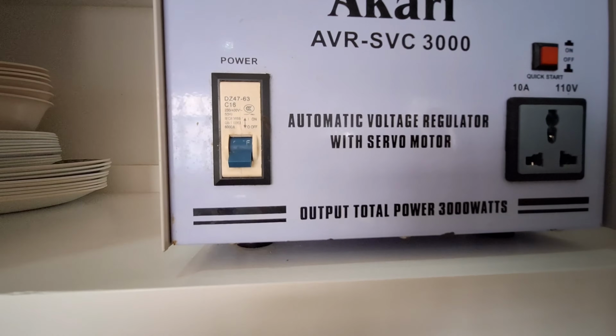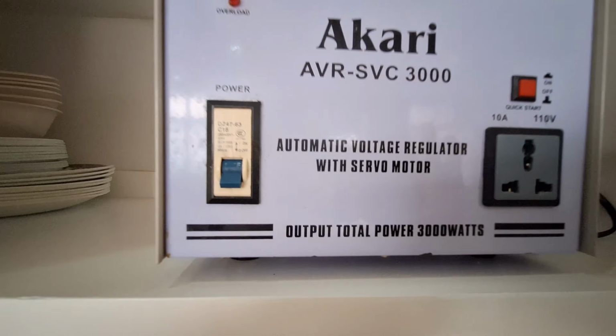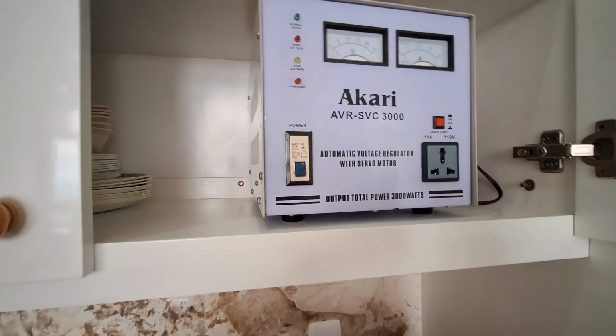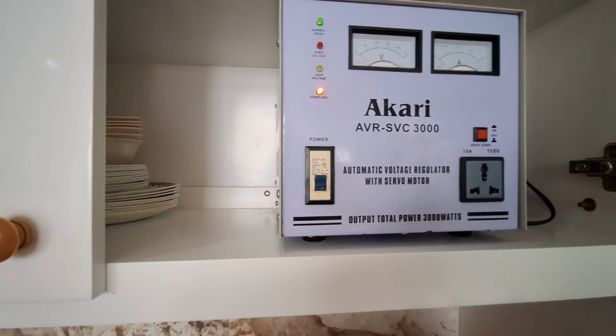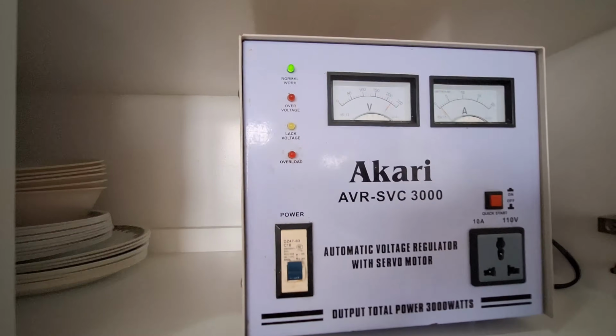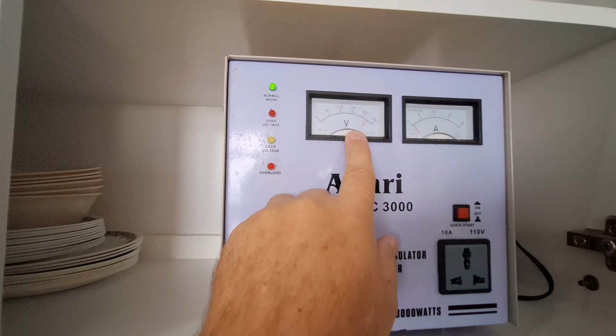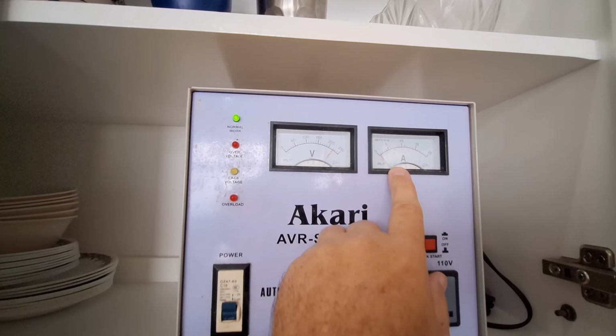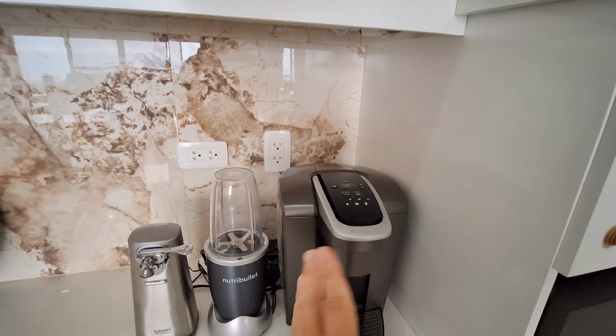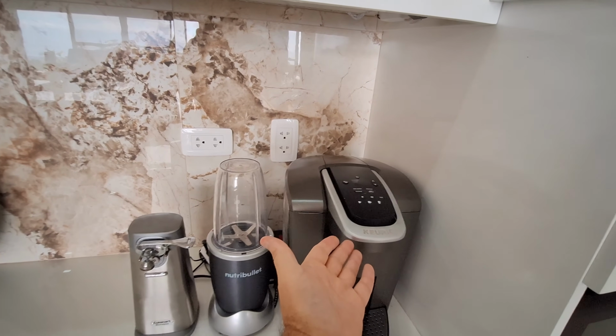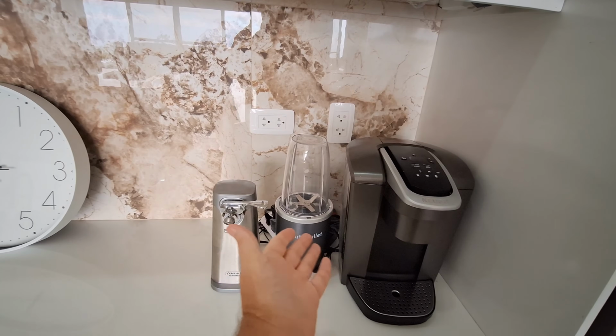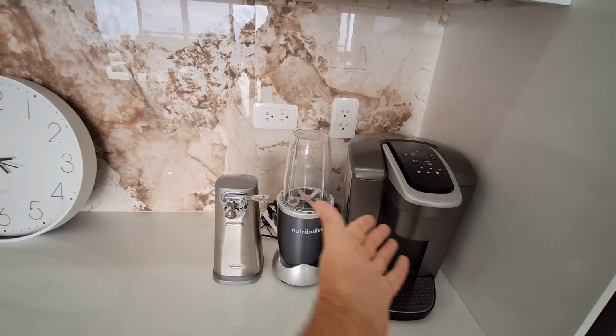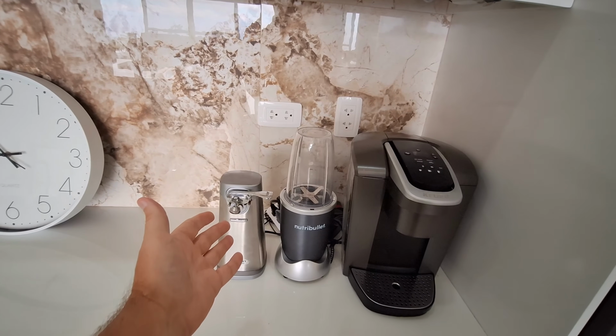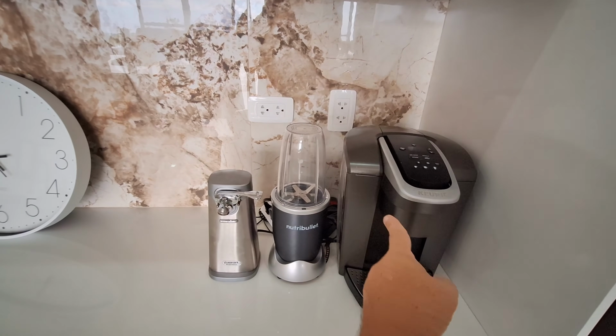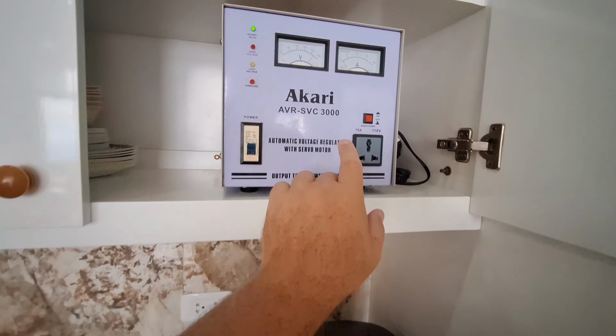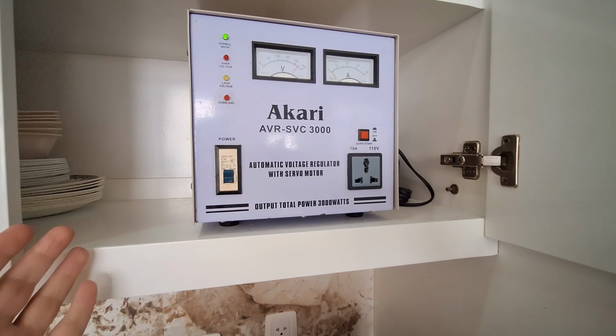So it's an automatic voltage regulator and also a step-down transformer - pretty simple. You put it on the circuit breaker, and you can see the 220 volts coming in with nothing going out yet. If I turn this on, which is a heating element, say 800 to 1,000 watts, and these other devices are probably less than 100 watts each, that's about 1,200 to 1,300 watts of draw if all three are on at once. This unit can handle 3,000 watts, so we shouldn't have a problem.